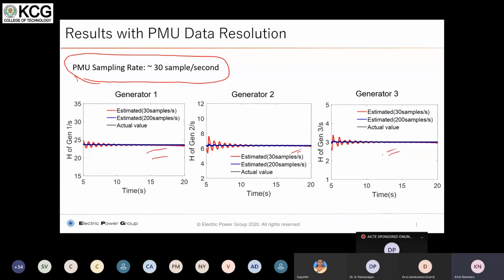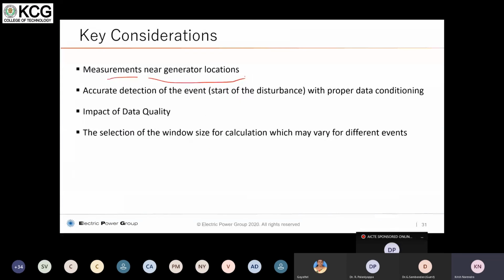So the key considerations are measurements closer to each generator location, or area-wise if you look at each area, and accurate detection of the event, meaning the duration of the event and the starting point of the disturbance. The data quality of the PMUs has to be observed very closely to implement this method, and the selection of time window and size also has to be done properly. So these are some of the key considerations in this methodology.